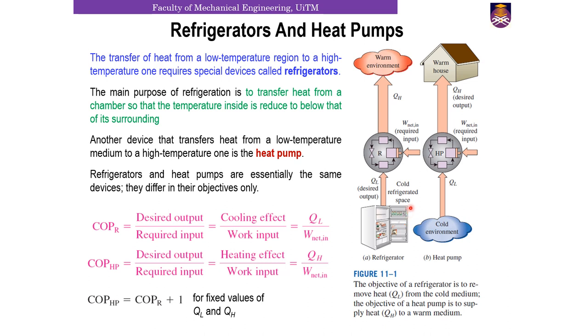So a typical house with an area of 200 meters squared, you will have a cooling capacity load of almost 3 ton, and that translates to about 10 kilowatt. And you can use this value to design the refrigeration system that you need for the air conditioning purposes, which we will cover next.